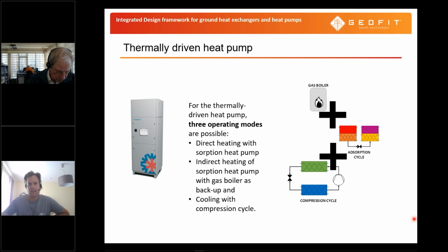So the coupling now, this is the innovation, the coupling of an adsorption and a vapor compression unit within this hybrid heat pump system. This gives us a certain flexibility in operation modes. So in order to find the best solution for each pilot and also for the integration, the colleagues from CNR and from Fahrenheit have evaluated more or less 3 operation modes. So either direct heating with the adsorption heat pump, or indirect heating with gas boiler and backup, and cooling with the compression cycle. Yeah?